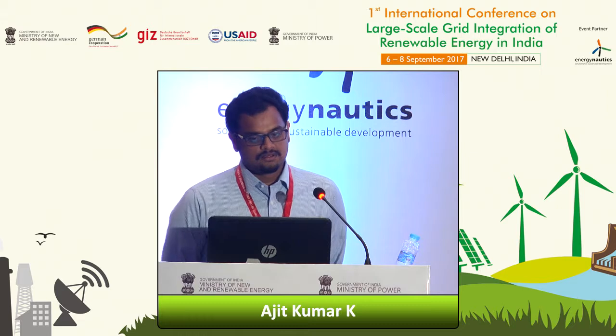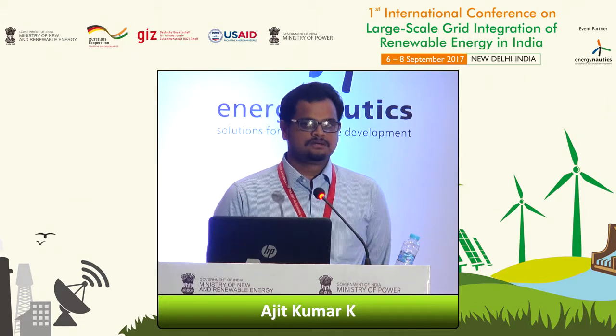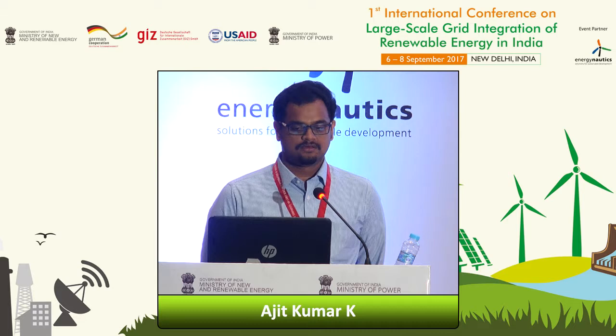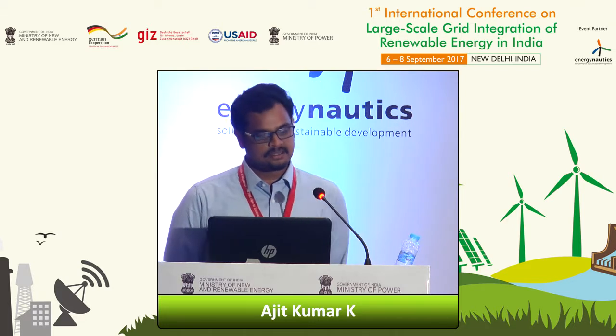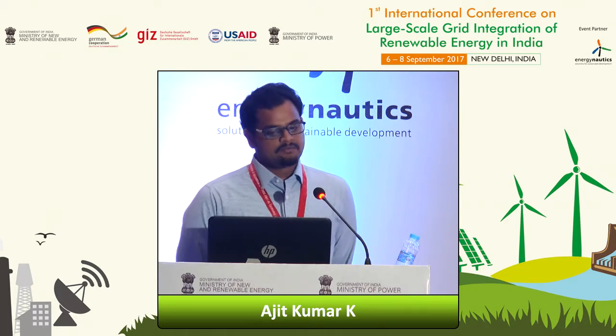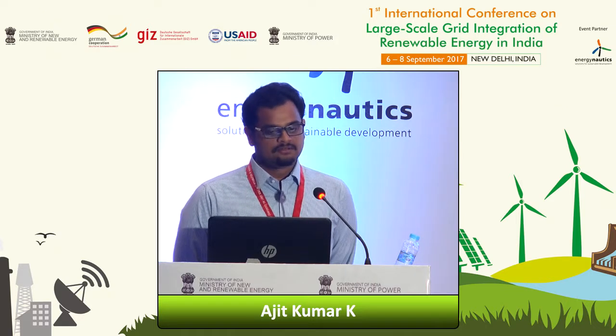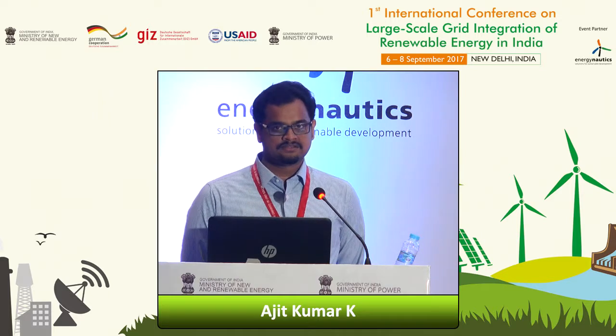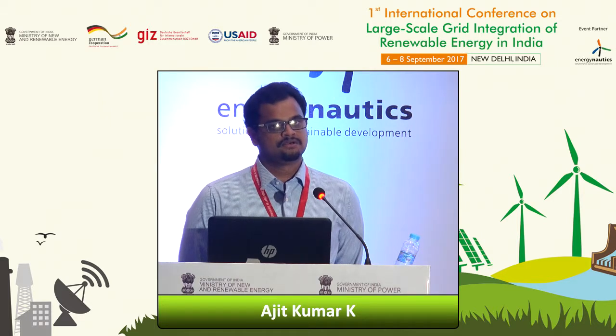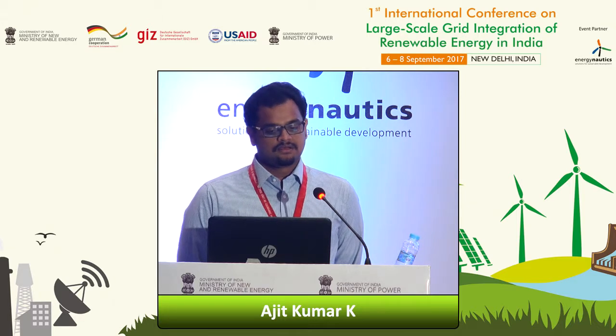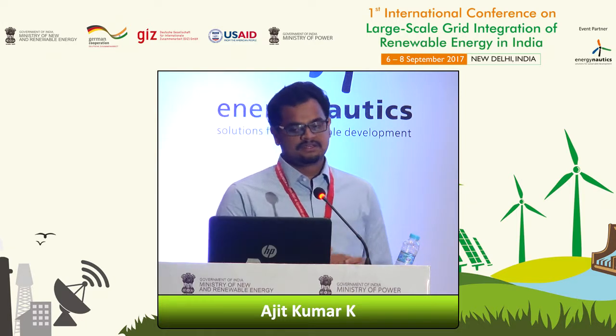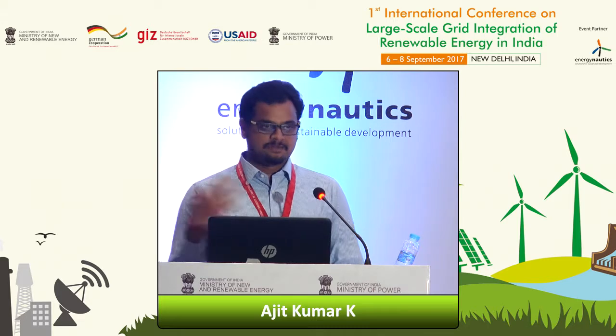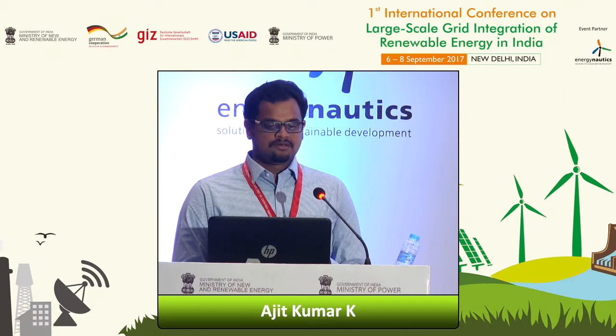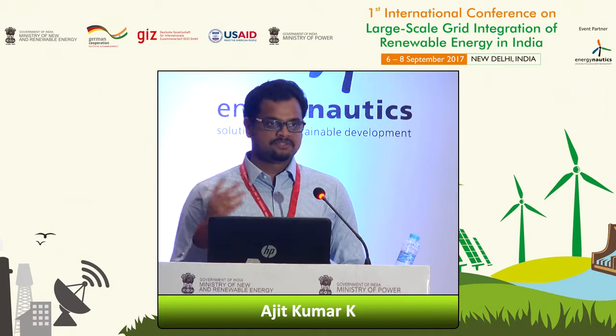Problem statement. Until recently in India, solar PV installations were connected only at distribution level, but large solar parks of hundreds of megawatts are coming up and they are connected at transmission level. Solar PV, unlike thermal plants, is asynchronously integrated to the grid through inverters, and hence does not contribute to grid inertia. It is a significant aspect of the conventional counterparts, wherein the grid inertia is the primary response for frequency stability.